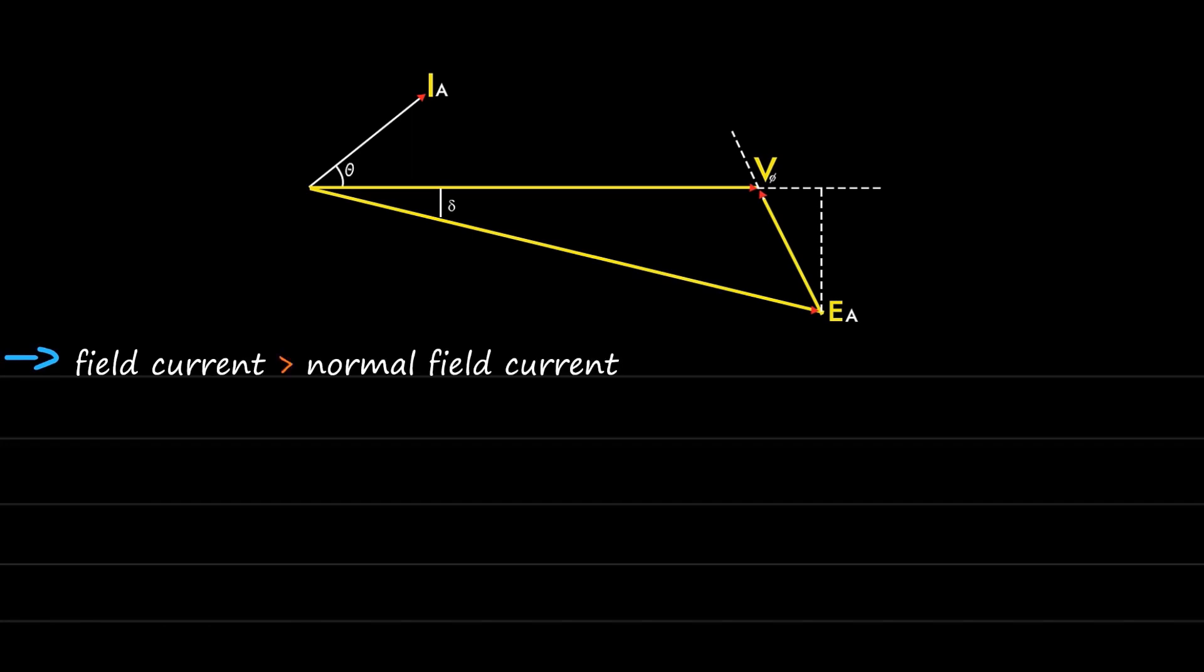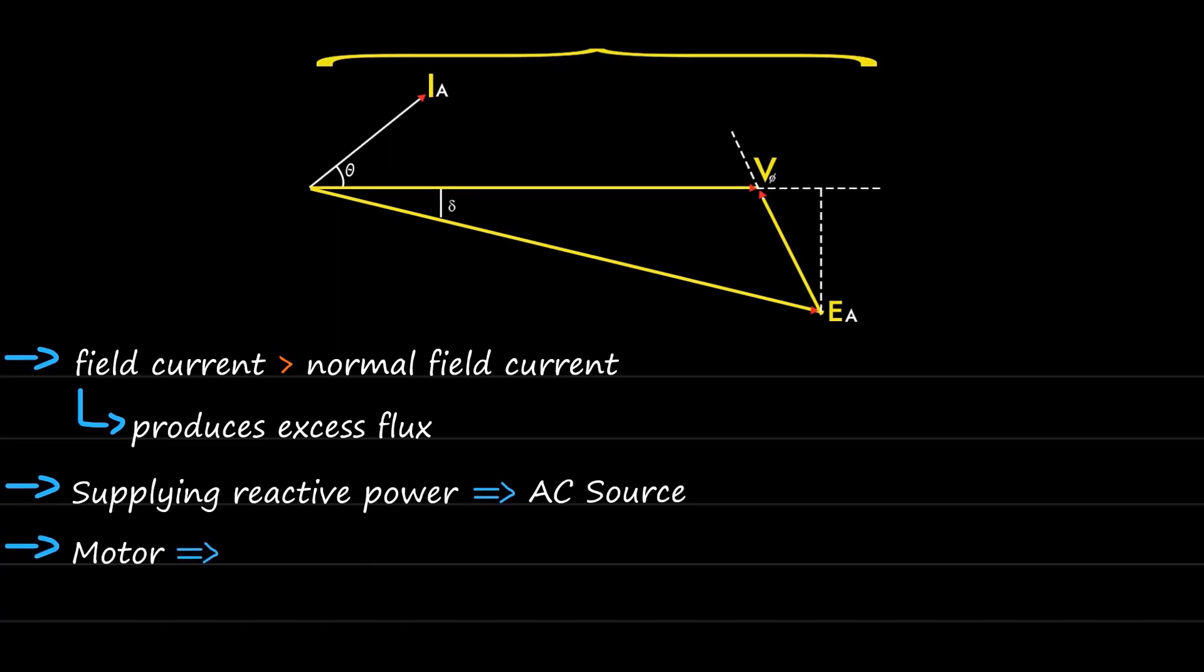If the field current is more than the normal field current, this excess amount of field current produces excess flux. This results in supplying reactive power to the AC source, and the motor in this case is said to be operating at leading power factor, and thus said to be overexcited.